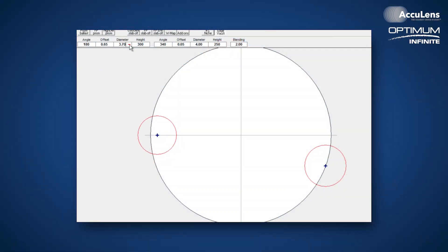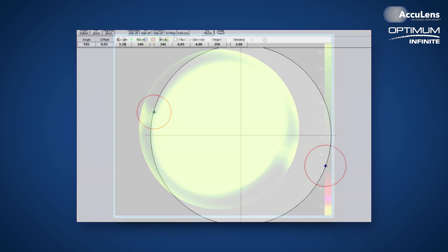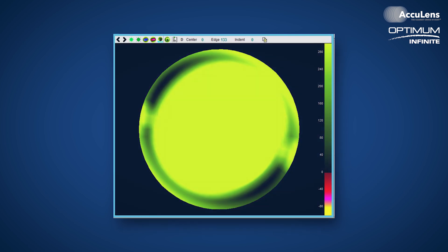From here, we program the AccuVault into the design. At AccuLens, we can build an AccuVault at any radial location, and in most cases the vault starts around three millimeters wide, about 300 microns deep, at the lens edge. Each vault is completely customizable, and we can incorporate up to two AccuVaults per lens — so you can have a temporal and a nasal vault if needed. These modifications are compatible with all our scleral lens platforms, including lenses with front surface toric correction, multifocals, or a combination front surface toric multifocal scleral lens.